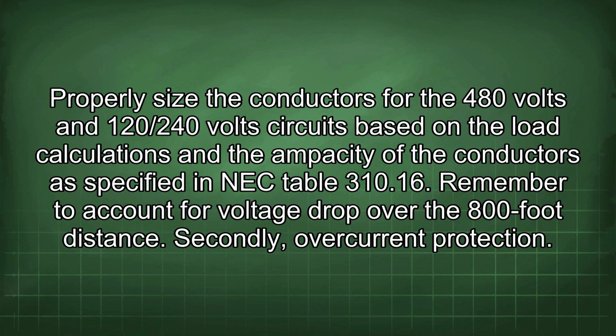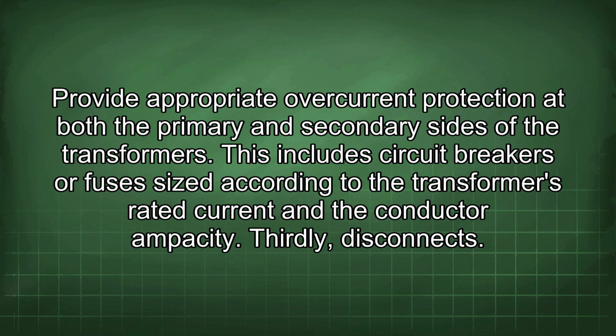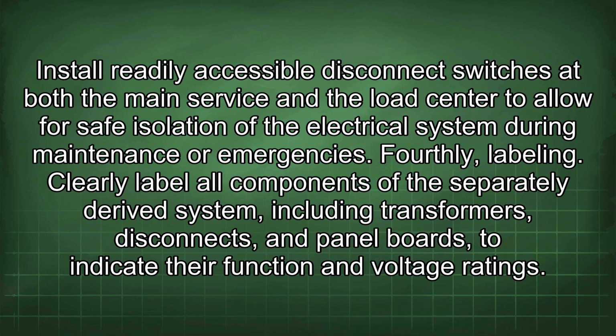Secondly, overcurrent protection. Provide appropriate overcurrent protection at both the primary and secondary sides of the transformers. This includes circuit breakers or fuses sized according to the transformer's rated current and the conductor ampacity. Thirdly, disconnects. Install readily accessible disconnect switches at both the main service and the load center to allow for safe isolation of the electrical system during maintenance or emergencies.